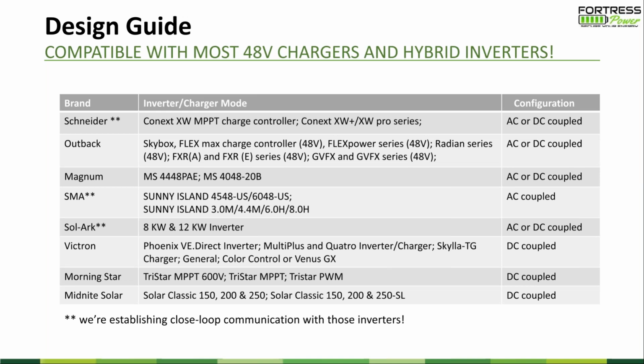The first thing is compatibility with current inverters in the market. We produce a 48-volt energy storage battery, and it's compatible with most 48-volt inverter storage products -- for example, Schneider, Outback, SMA, Magnum, Sol-Ark, Victron, Morningstar, Midnite Solar. I don't know what the major brand is in Africa, but if you have a new inverter, send us an email and we'll help you look at the specification, help you size up the system, help you do the parameter setting, and check if it's compatible with our battery. Usually the rule is that most configurable charge controllers for a 48-volt system are compatible with our battery, so it's not a big concern -- if the inverter takes 48-volt batteries, most likely it will work.